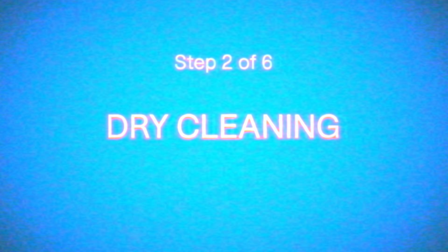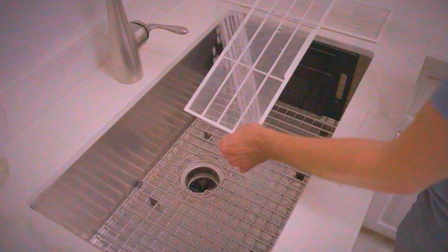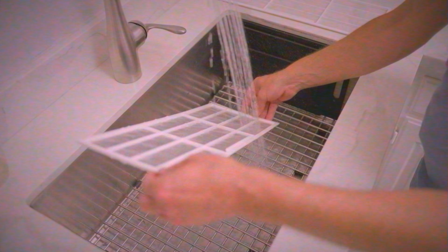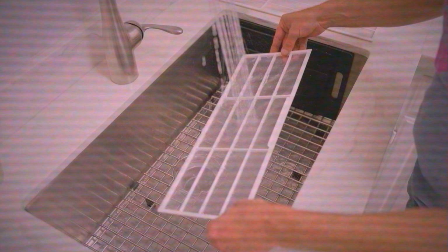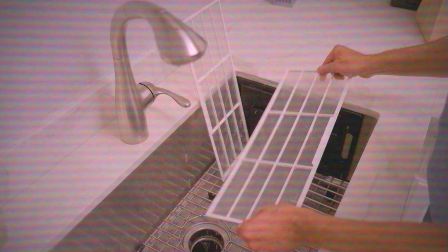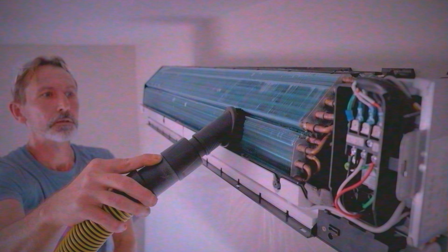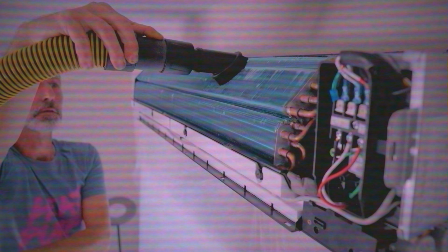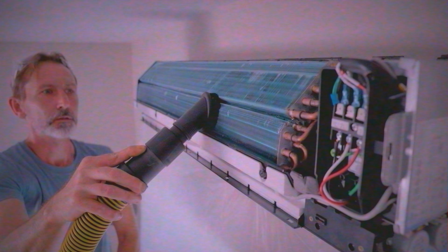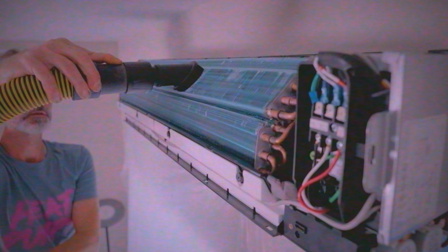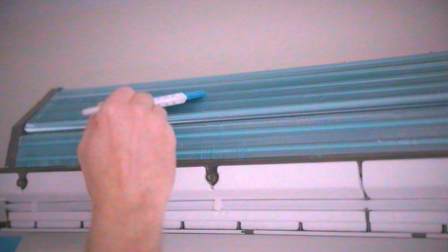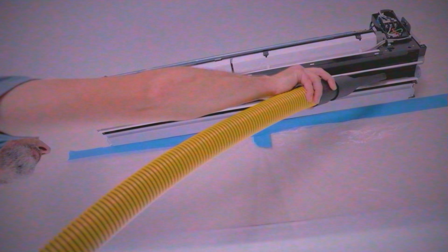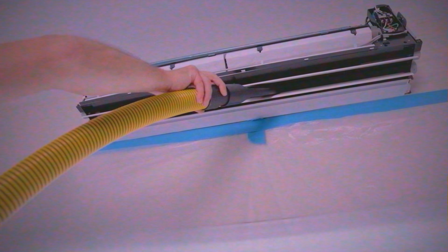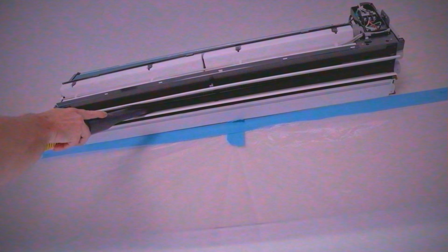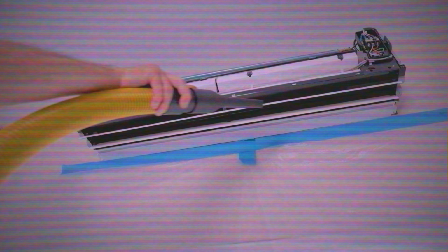Start by cleaning the air filters. Shake out any debris and rinse the filters in a sink to loosen trapped particles. Let the filters air dry before reinstalling. Then, using the brush attachment, gently vacuum the heat exchanger using up and down strokes to avoid bending the delicate coil fins. If needed, use the soft bristle brush to dislodge dust. Then, using the crevice attachment, vacuum the area beneath the blower fan and around the finger guard.